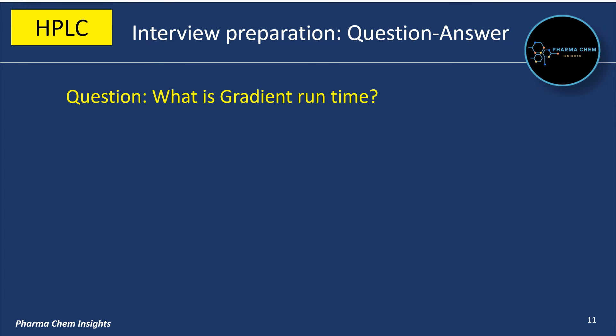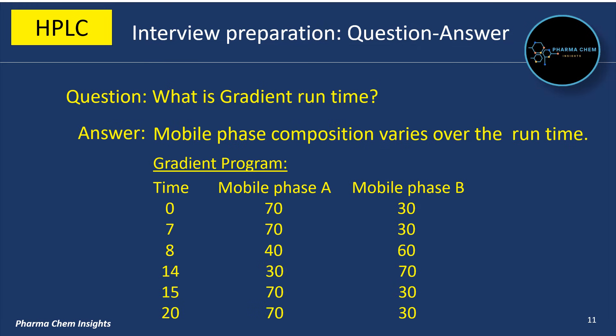What is gradient run time? In gradient run time, the mobile phase composition varies over the run time. For example, in a gradient program method of 20 minutes: from time 0 to 7 minutes, mobile phase A to mobile phase B ratio is 70:30. At 8 minutes, it changes to 40:60. At 14 minutes, it changes to 30:70. At 15 minutes, it changes to 70:30. And at 20 minutes, it comes back to 70:30 ratio.